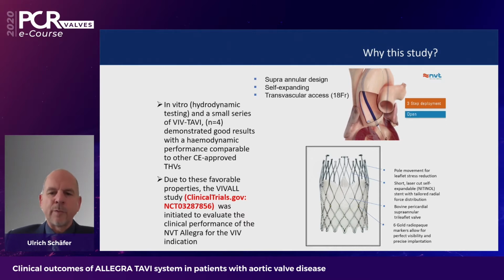So why was this study performed? Just looking at the stent design of the ALLEGRA transcatheter heart valve, with this tubular stent design, it is apparent to most TAVI operators that this stent might be particularly appealing for valve-in-valve implantation. The stent consists of a short laser-cut self-expandable nitinol stent frame. It carries a bovine pericardial tissue valve, being a tri-leaflet valve, and it also has 6 gold markers, which are radiopaque and allow for better visibility during implantation. In addition to that, the stent has some pole movement in the top to possibly translate into a better longevity in the future for these particular valves.